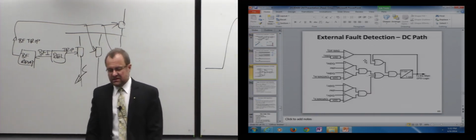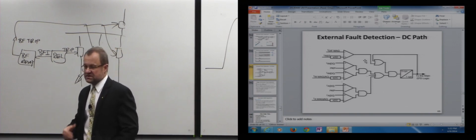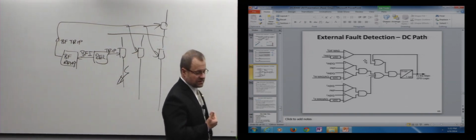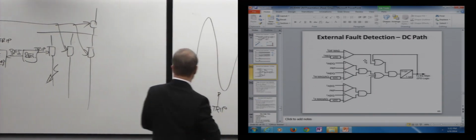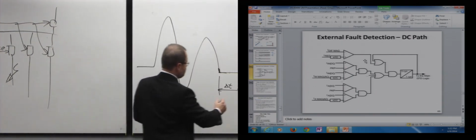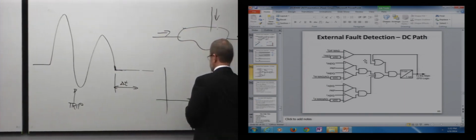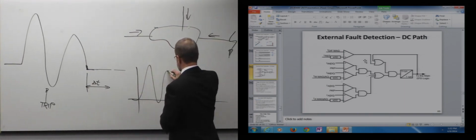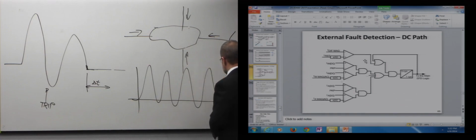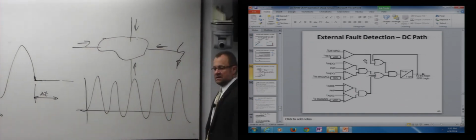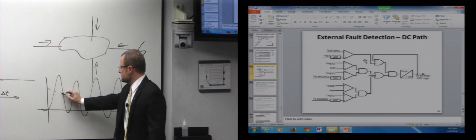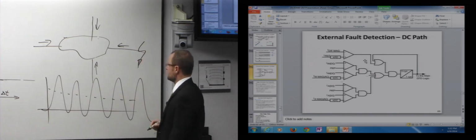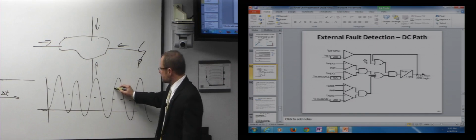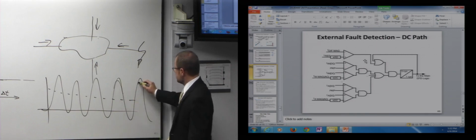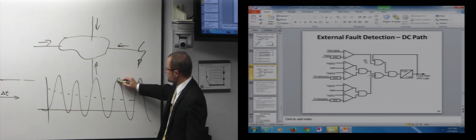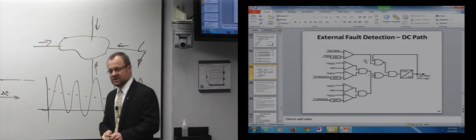I will skip that. The second type of saturation is DC saturation. So again, what that means is I have a current that is small, but it's offset. And that offset is not going away fast. So I effectively have a slowly decaying DC offset in this current. And what will happen is it will start saturating the CT, and I will start seeing that error eventually. So what will be the best way to detect that?